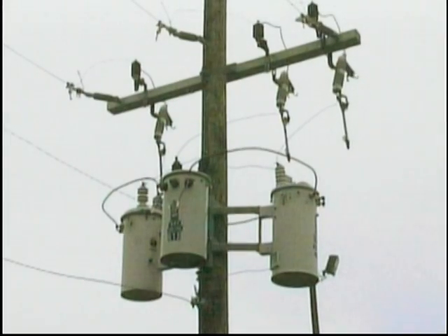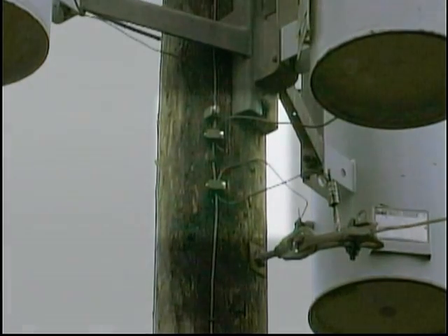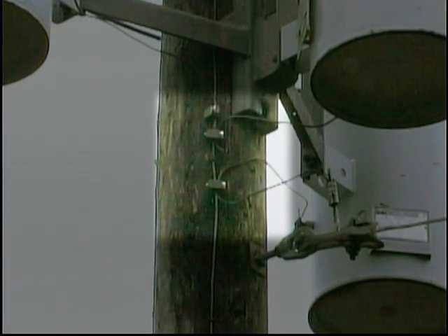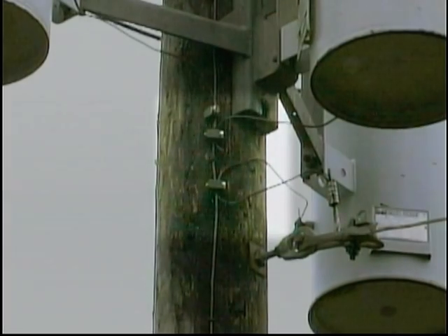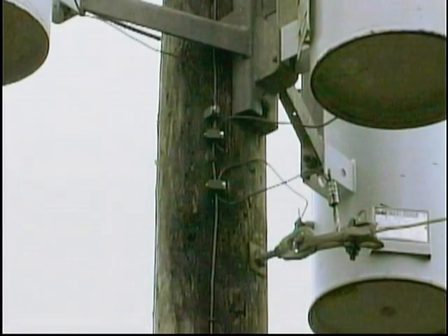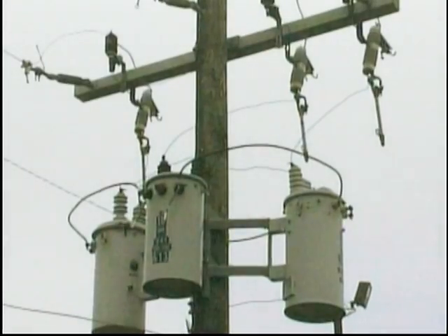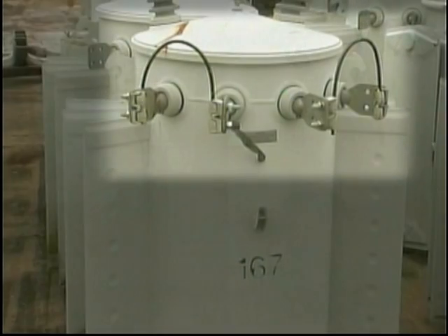Here's the 3-phase bank we'll work on. We can tell this is a Y primary connection because one end of the primary windings has been Y tied at the case ground and connected to the system neutral. We can also see the other end of each primary winding is connected to a phase of the 3-phase system. When properly connected, the bushings on each transformer will look like this.